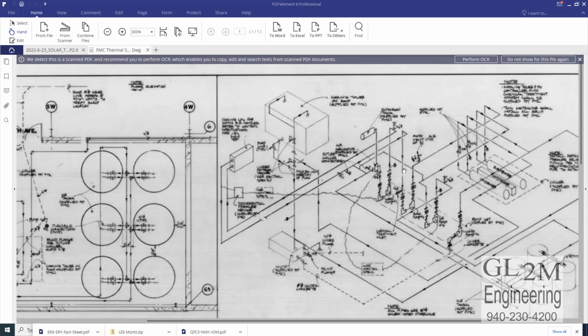even 20 degrees, water, as you know, is not compressible, and so pressures can climb catastrophically quickly. And what usually happens is a valve will fail and the system will start flooding the building, and obviously the chiller plant goes down. So these are critical things that you have to have in any good chiller plant.